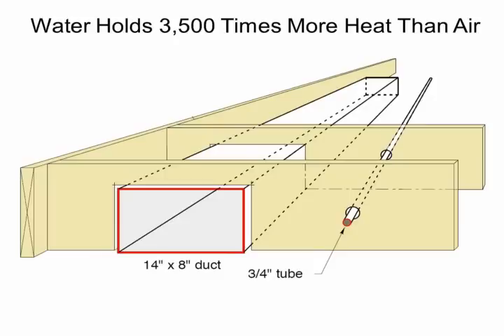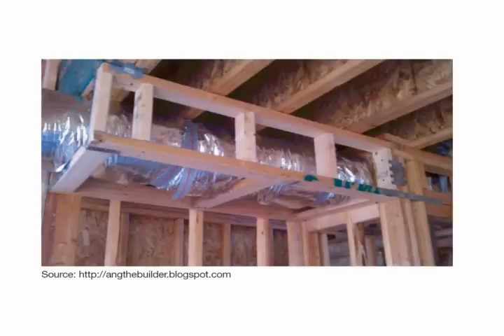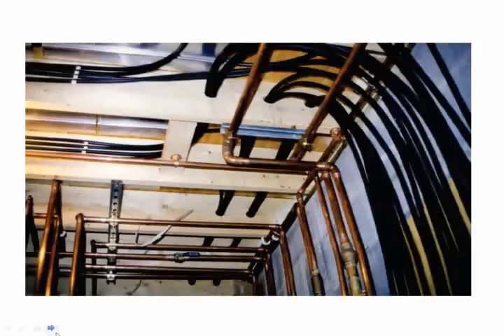Why do we love hydronics? Well, you can send a lot of heat from point A to point B by way of hydronics as opposed to, as an example, by way of air. And in doing so, we don't have to be so invasive with running heat from point A to point B in a building. So it takes a lot less construction to route heat using hydronics than air as an example. So here's a shot of some duct work, very invasive, if you will, as opposed to a hydronic system. So hydronic systems are efficient from that standpoint.